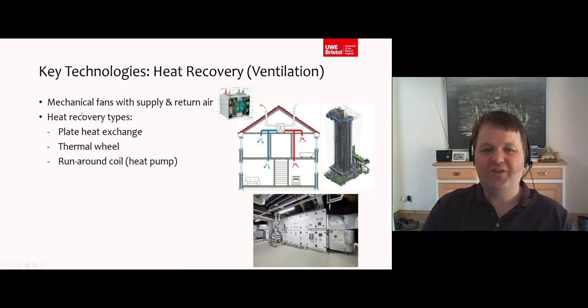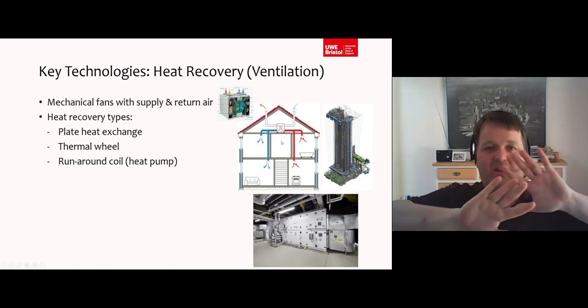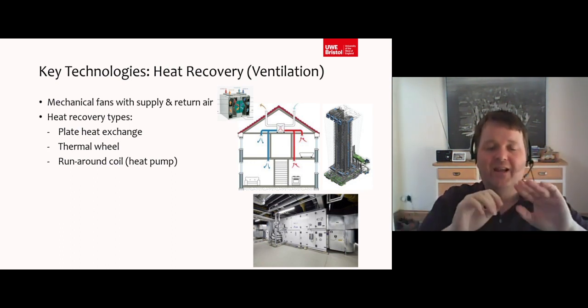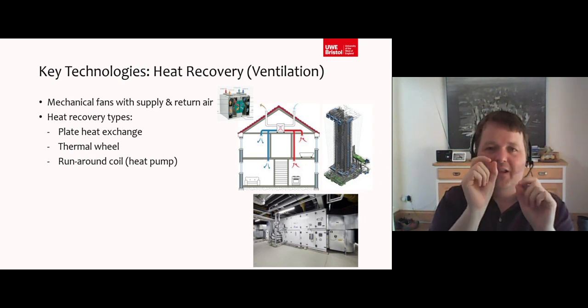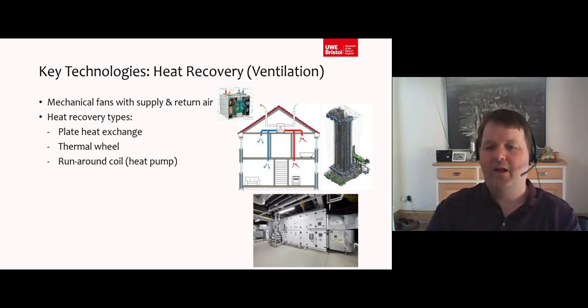In commercial systems, there's three main types of heat recovery. There's plate heat exchangers, which is what is on a domestic level MVHR. They come close to each other through plates, metal plates. They don't mix the exhaust air and the fresh air. The heat goes through the metal, and that's how the heat exchange happens.